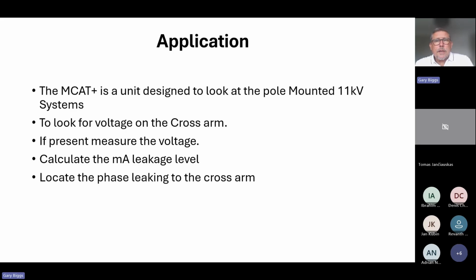And what we're going to do this morning is I'm going to explain why 11 kV wooden pole mounted systems are different to either concrete or metal systems. The idea of this product is to check the voltage on the cross arm. So we'll be attaching to the cross arm itself and checking if voltage is present. If voltage is present, we then look to calculate the milliamp leakage level, which together with the voltage gives us an indication as to the danger level that the system poses at that point. And then we would look to locate which of the three insulators attached to that system has actually gone down.